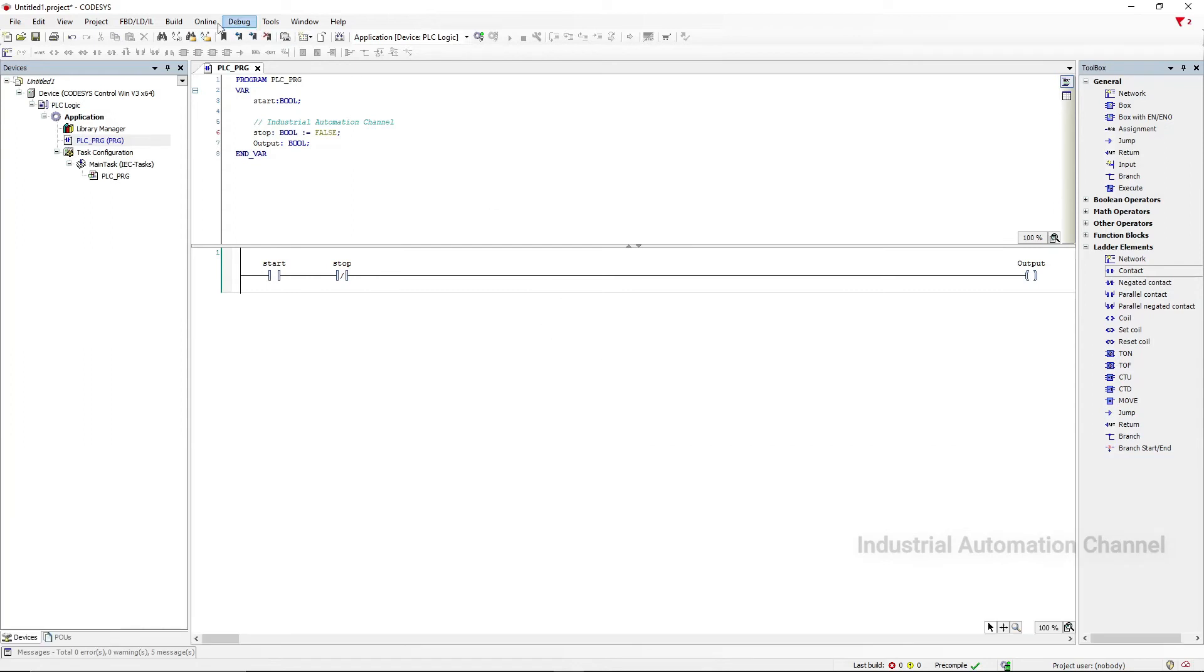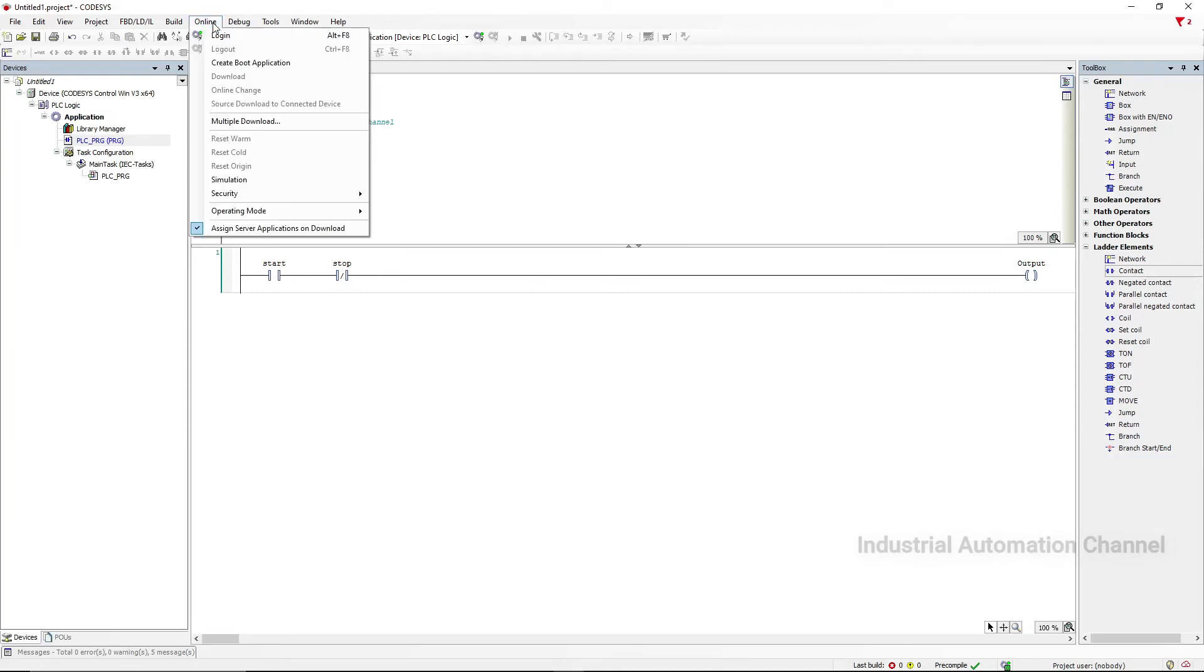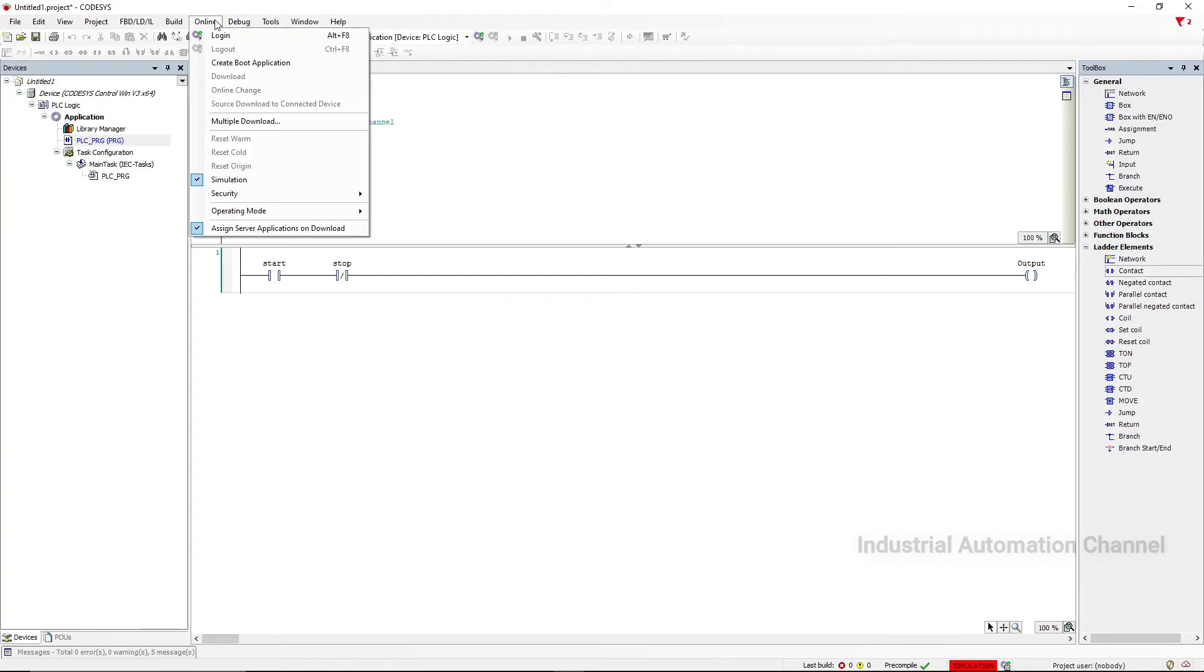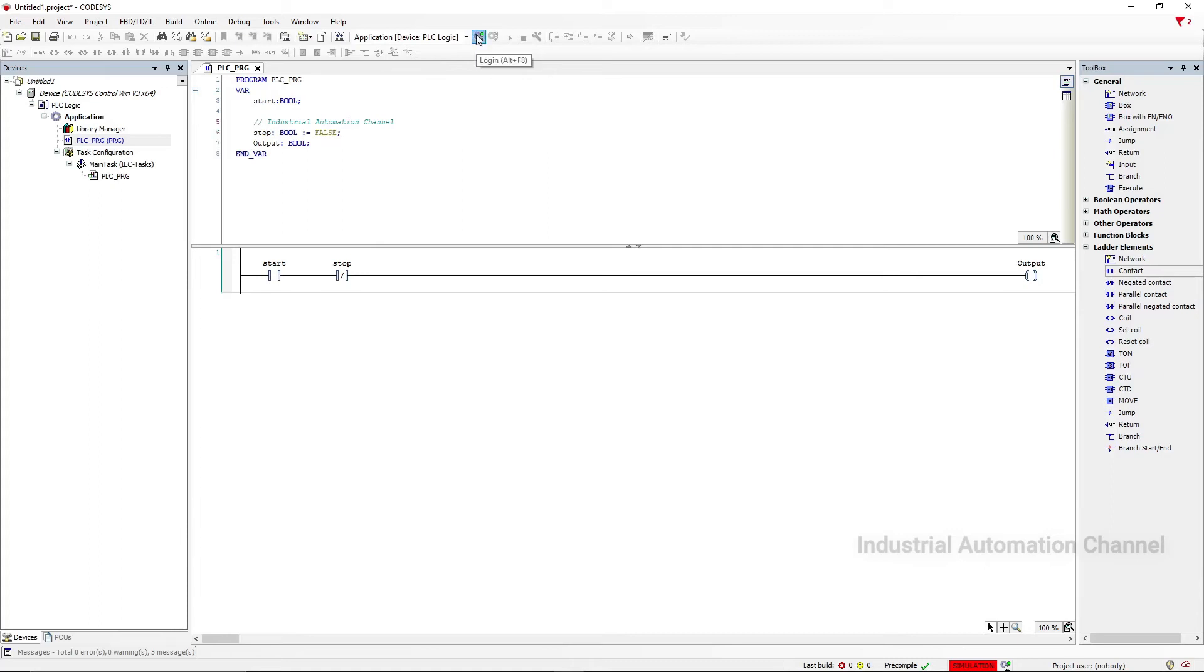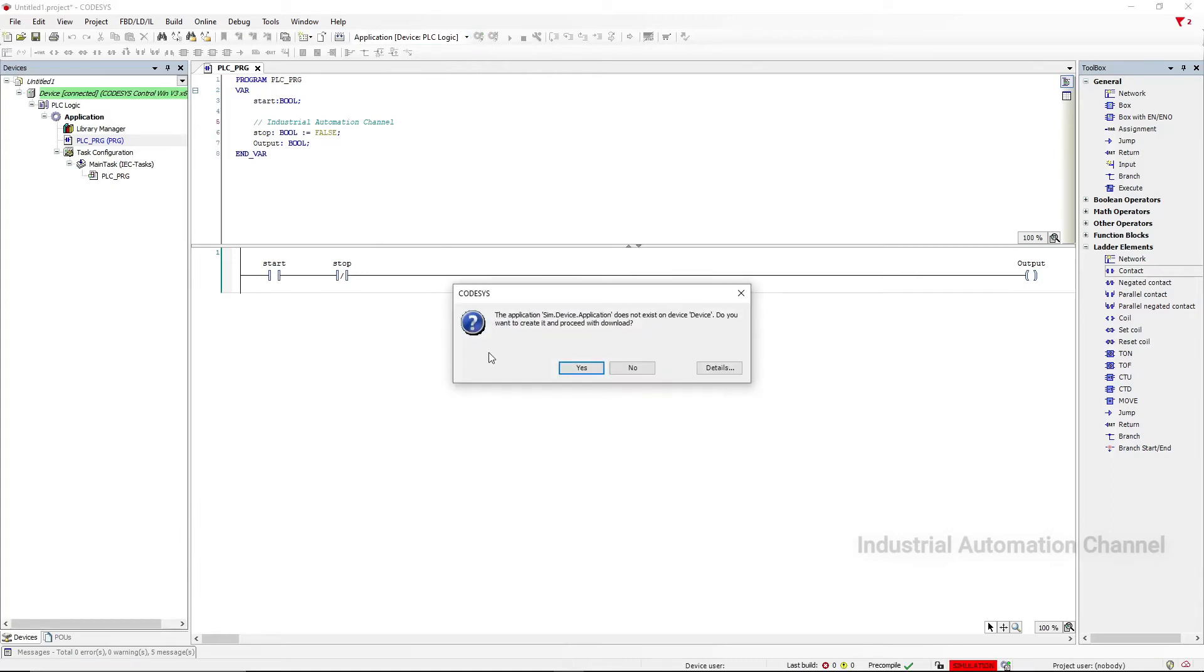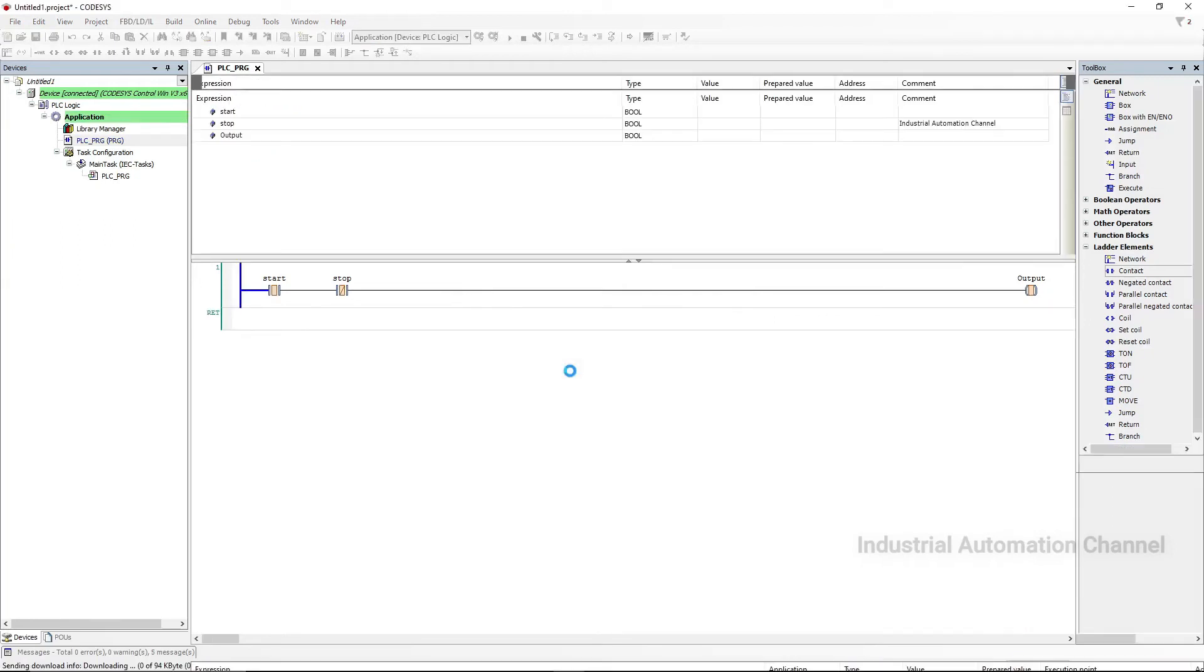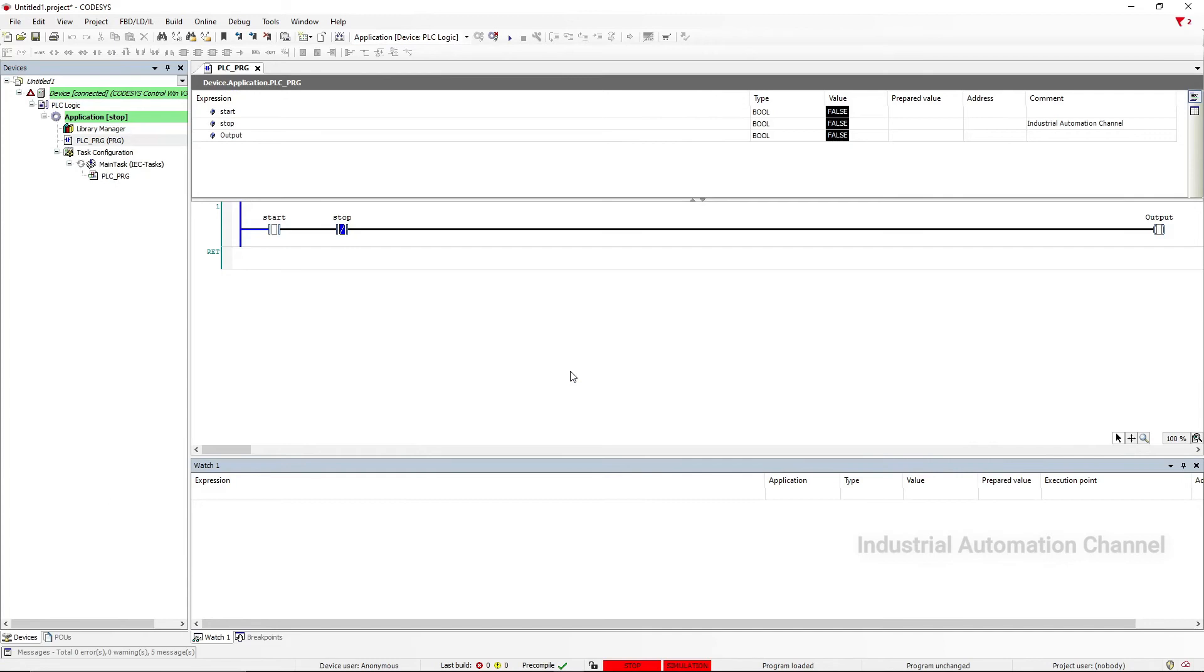Let's simulate our program. Go to Online menu, select Simulation. We can see in the bottom right corner that Simulation is turned red now. Then we need to download the program by pressing Login. You can also find it here in Online. It's going to find the Control V3. Hit Yes. So right now on the bottom we are Stopped and still in Simulation mode. Let's run the program. To start the simulation click on the Start sign here. Now we are in Run mode.